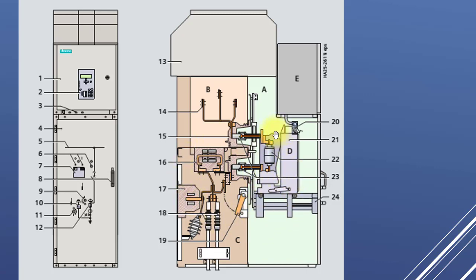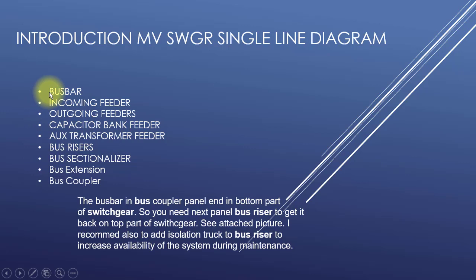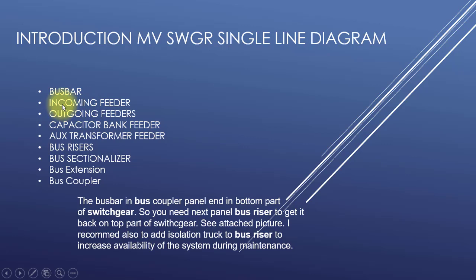Let me discuss the single line diagram technologies for MV switchgear. In MV switchgear we can see there is a bus bar, an incoming feeder, outgoing feeder, capacitor bank feeder, auxiliary transformer feeder, bus risers, bus sectionalizers, bus extension, and bus couplers. The incoming feeder is where power is fed to the switchgear — for example, if 11 kV is connected to the 11 kV side of a power transformer or a generator feeding the MV switchgear.